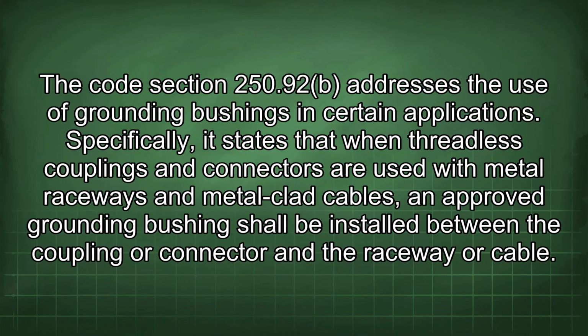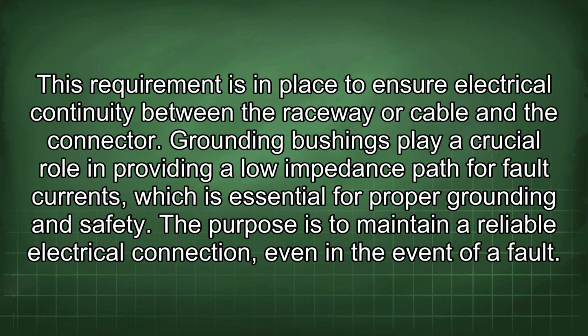Code section 250.92 addresses the use of grounding bushings in certain applications. Specifically, it states that when threadless couplings and connectors are used with metal raceways and metal-clad cables, an approved grounding bushing shall be installed between the coupling or connector and the raceway or cable. This requirement is in place to ensure electrical continuity between the raceway or cable and the connector. Grounding bushings play a crucial role in providing a low impedance path for fault currents, which is essential for proper grounding and safety. The purpose is to maintain a reliable electrical connection, even in the event of a fault.